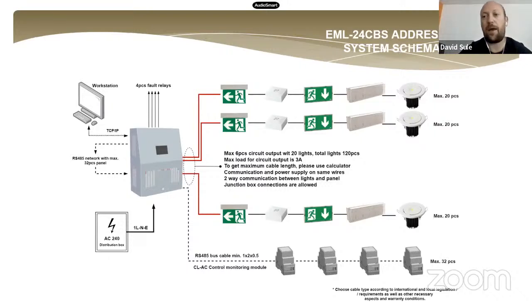The workstation and the programming laptop can be connected with TCP/IP to the panel. It's just a simple network cable. The panels can connect to each other over an RS-485 network and a TCP/IP network too. All panels have 4 fault relays, and the panel has a Modbus communication output to communicate with the BMS.